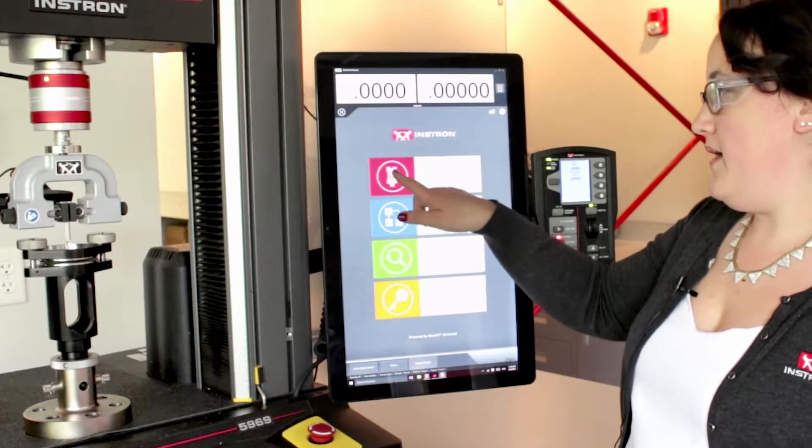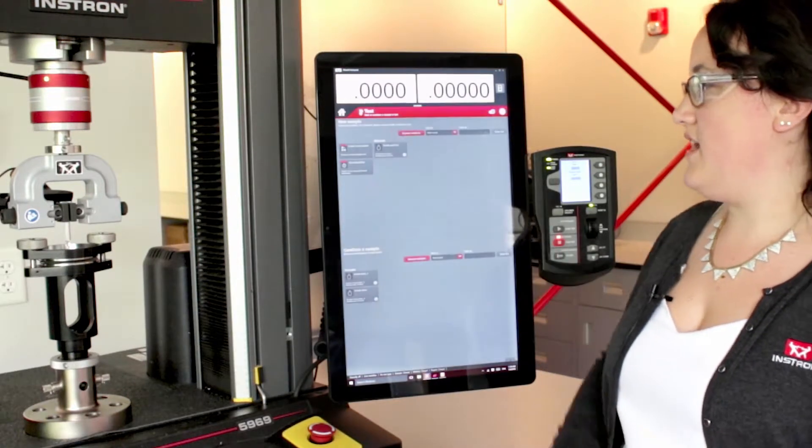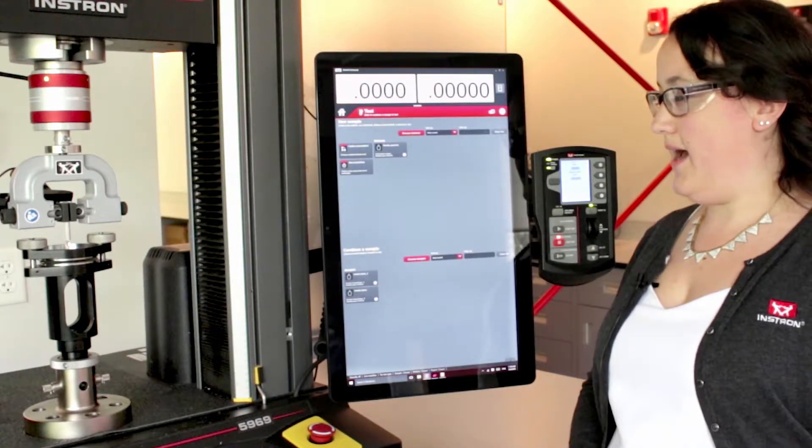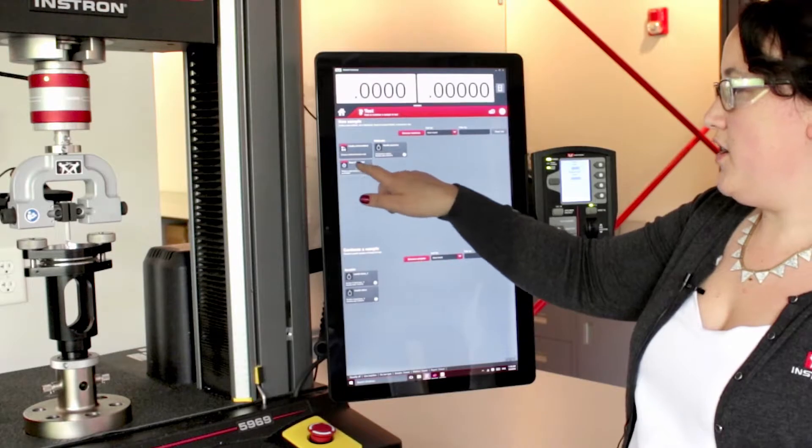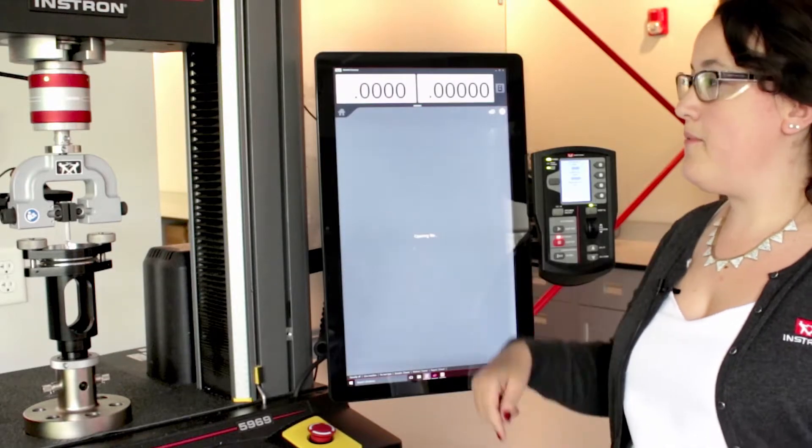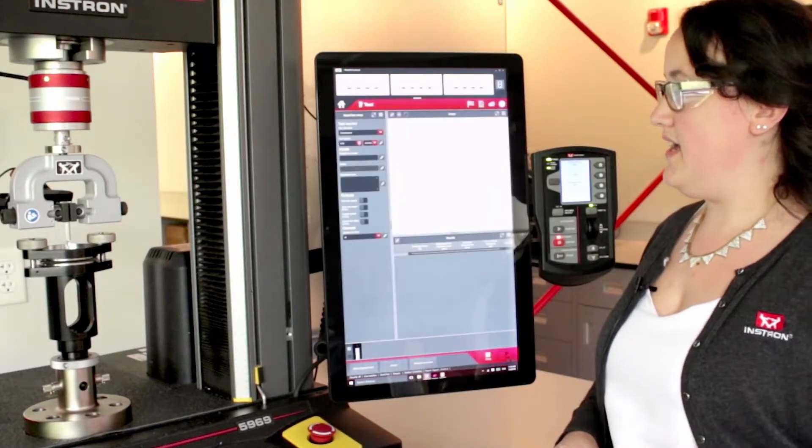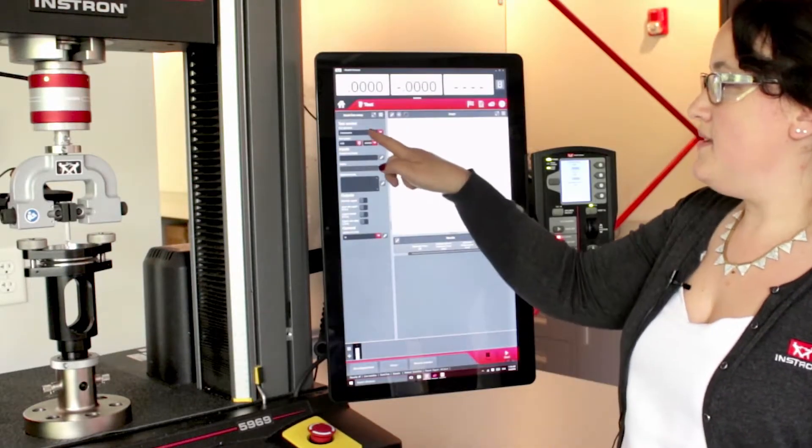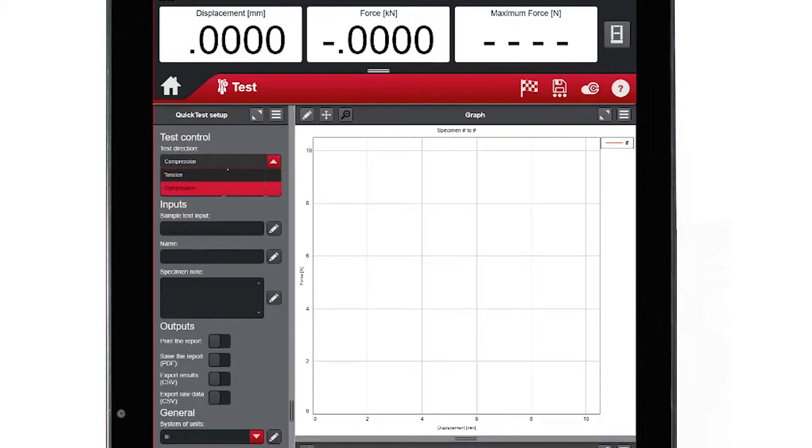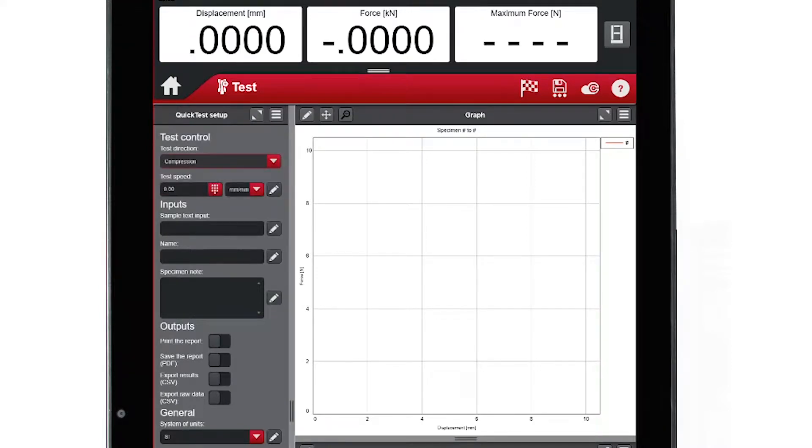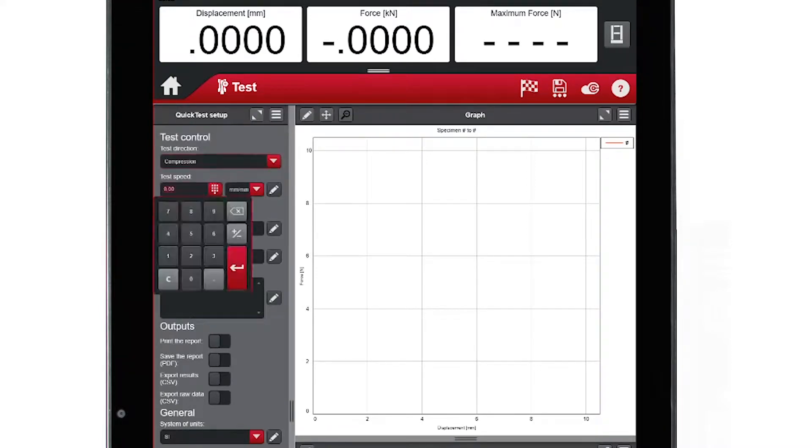Most operators will spend the majority of their time in the test tab. By choosing to run a quick test, operators can begin testing by simply choosing a test direction, either tension or compression, and choosing a test speed.